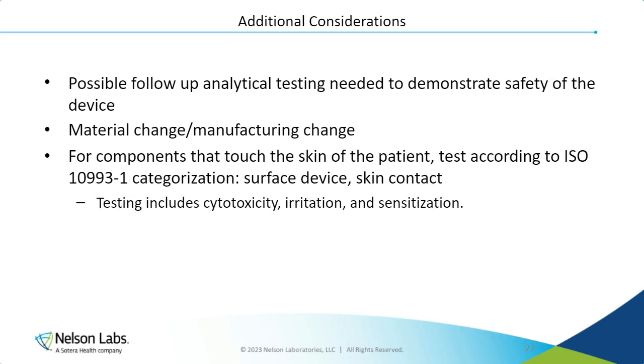If any components touch the skin of the patients, it could be a dual classification for that device as an indirect breathing gas pathway, as well as direct contact as surface device for the skin. A great example of this would be like a CPAP mask that fits on the face of a patient. This must undergo the VOCs and particulates, as well as the big three: cytotoxicity, irritation, and skin sensitization, as these three endpoints are not covered within the toxicological risk assessment.